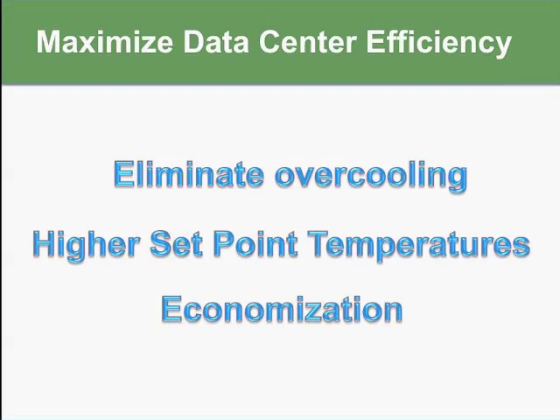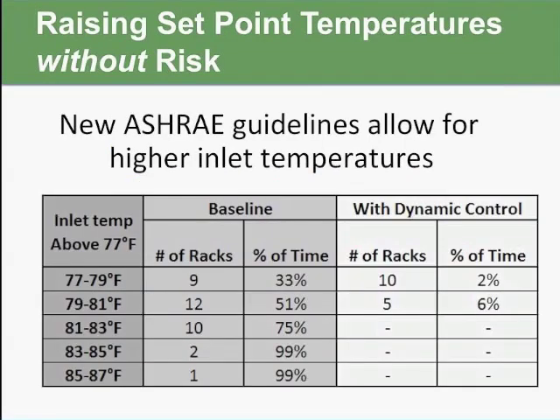And finally, you can implement air side and water side economization of your cooling system, because now you have tight control over the temperatures in the data center to ensure that you don't have any risk to your equipment through economization. Here's an example of a case study where they raised the set point temperature to 77 degrees, which clearly saves a significant amount of energy without risk to the equipment. But the key difference in this case study is what happens when you don't have any feedback control and visibility into your temperatures. In this case, they raised the inlet temperature to 77 degrees, and then the comparison is with dynamic control. In the baseline situation where you have no dynamic control, no visibility, you can see a significant number of the racks are above the targeted inlet temperature of 77 degrees for a significant period of time.